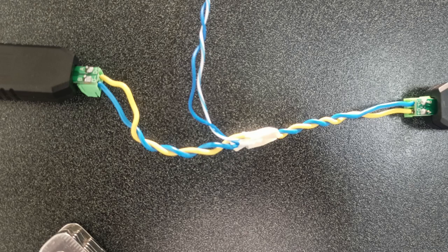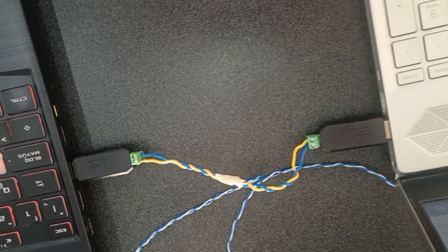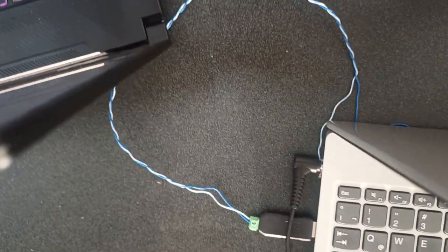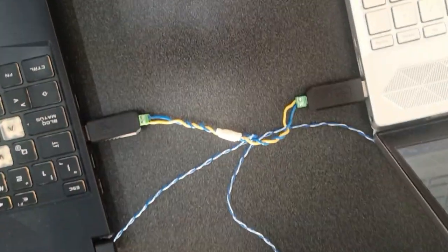To connect the master to slaves, a junction is used. The master communicates with more than one slave, and for this, a 120 ohm resistor is also placed in both the master and the last slave.